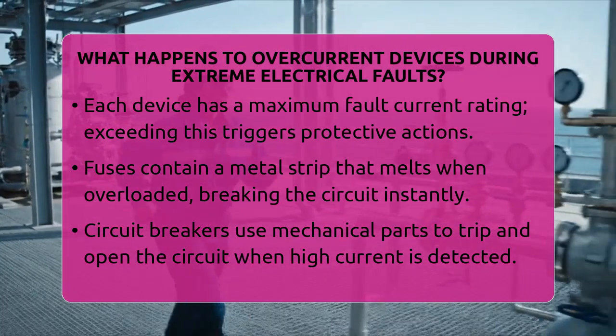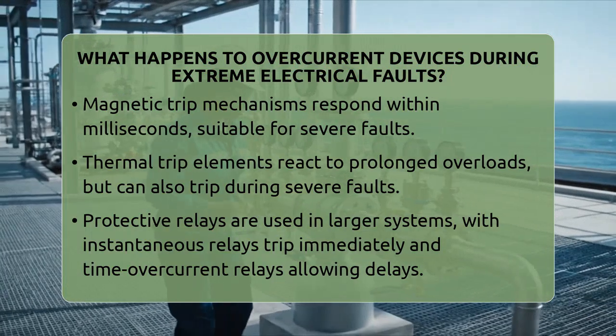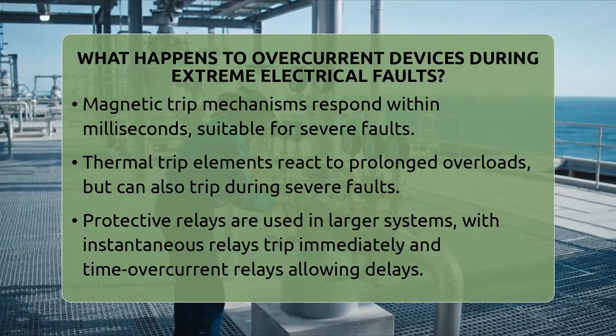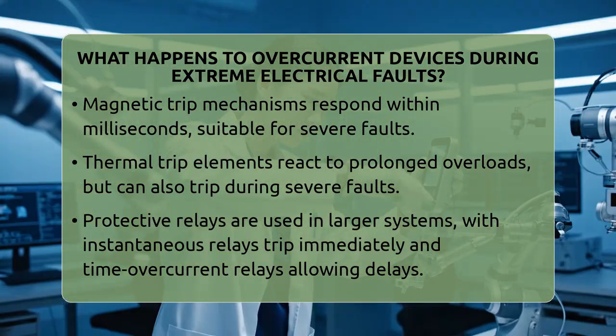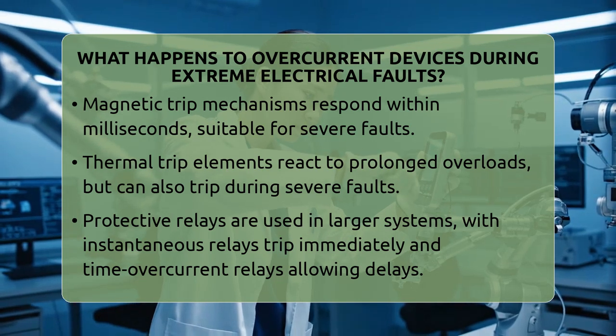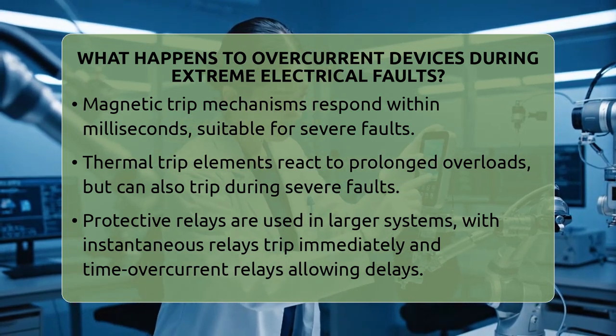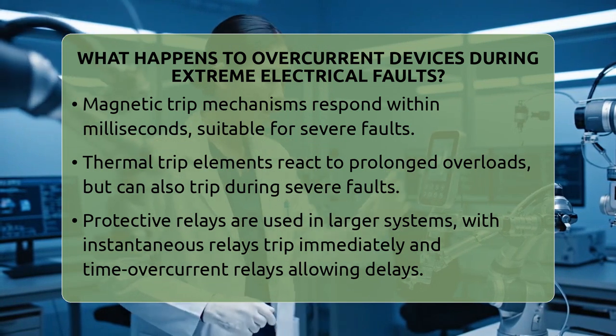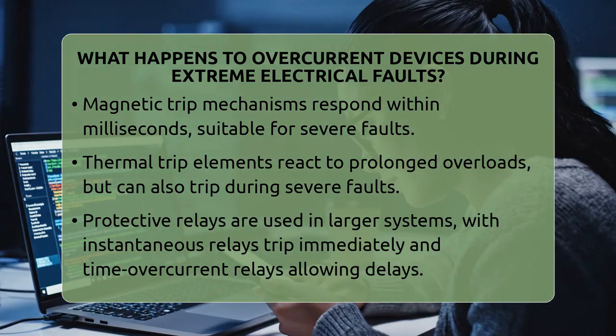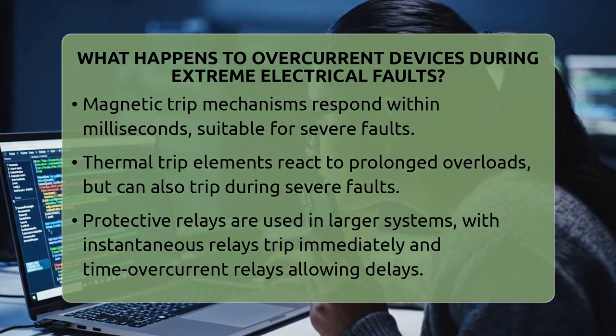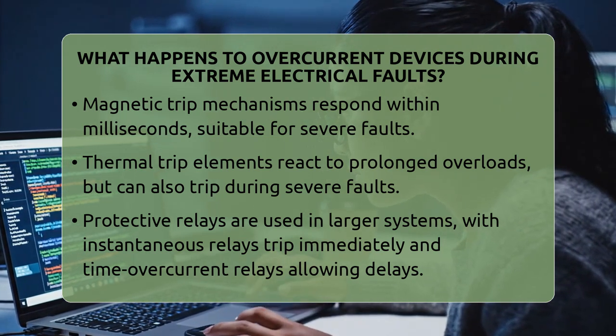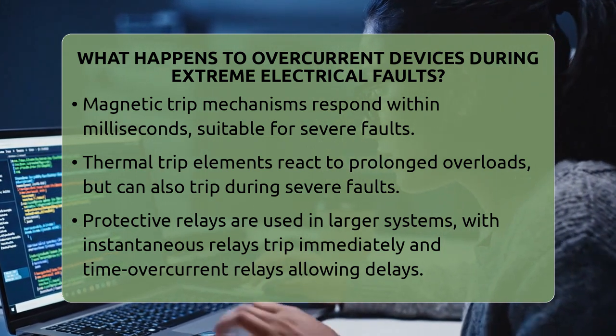Protective relays are used in larger power systems. Instantaneous overcurrent relays trip immediately when the current exceeds a set level, while time overcurrent relays allow a brief delay depending on the fault severity. During an extreme fault, these devices act swiftly to disconnect the faulty part of the system. This prevents the high current from damaging equipment further down the line.